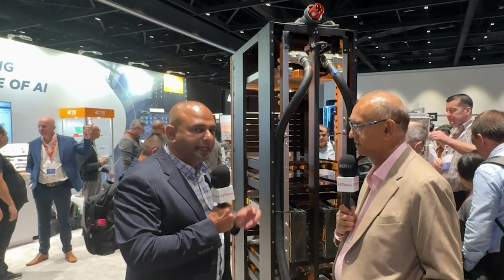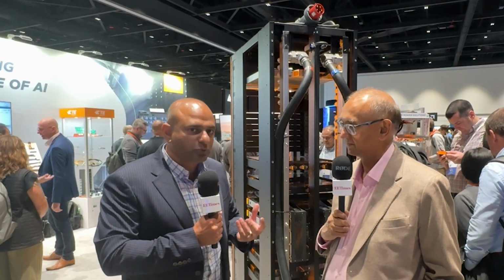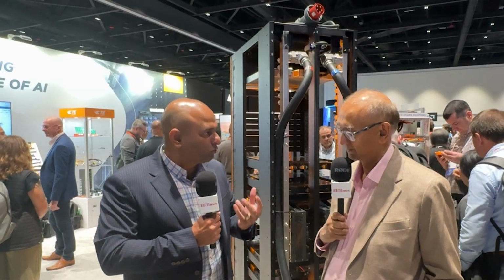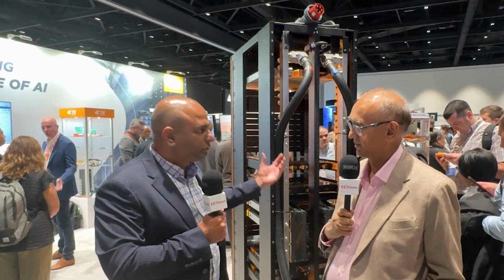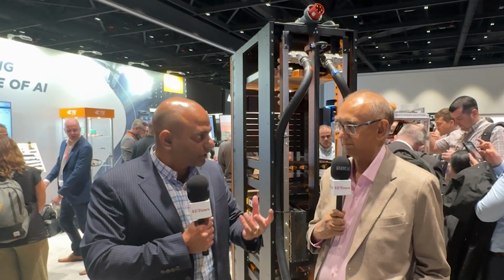What that helps with is powering a much higher power AI rack. Traditional air-cooled busbars can support up to 200 kilowatts in a rack. With liquid cooling, you could go much higher - 300 kilowatt racks, 400 kilowatt racks. And what that all means is more GPUs per rack, higher clustering, which addresses a lot of the AI challenges customers are facing.